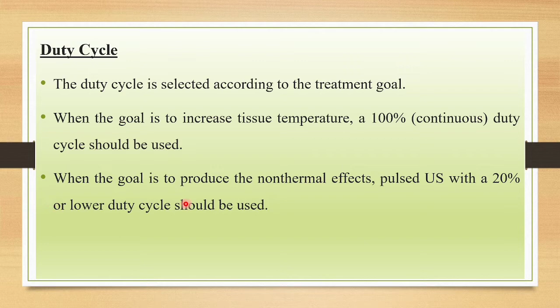It depends upon the ratio of on and off periods. Sometimes 20%, sometimes 40%, sometimes 60%, sometimes 80%. It depends upon the effect we need. So if our goal is to increase the tissue temperature, we need to use continuous mode ultrasound, which will have 100% duty cycle. And if the goal is to produce non-thermal effects, we can use pulse ultrasound with a 20% or lower duty cycle.